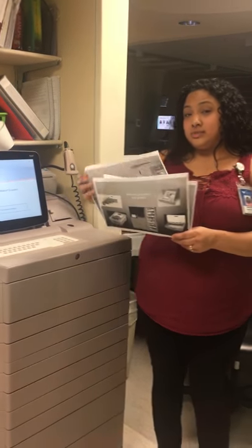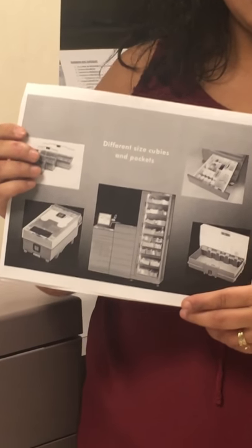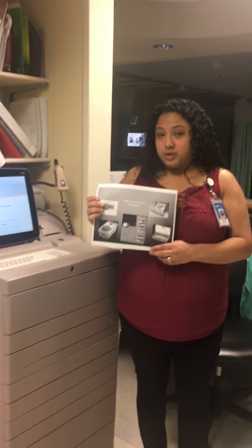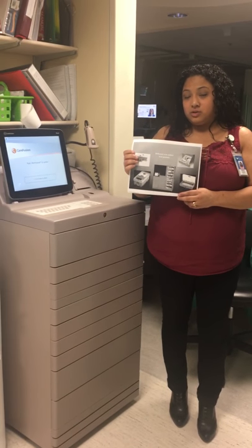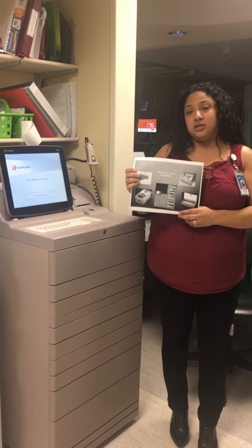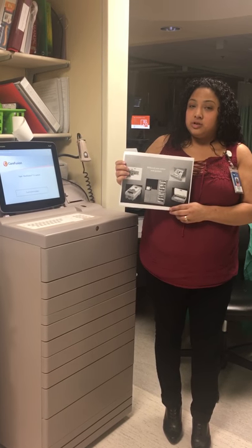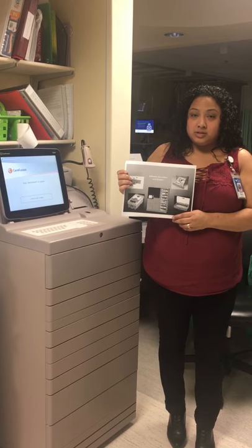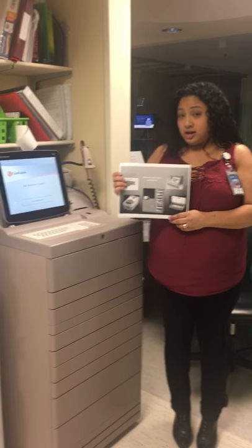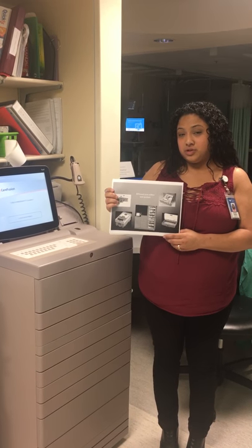Pyxis has different sized Cubies. It has 1x1s, 1x2s, 1x3s, and full height Cubies which are 2x1, 2x2, 2x5s, and 2x3s. We also have matrix drawers and towers. Depending on the medication, that is how you will load your medications. For example, you will load tablets in 1x1s, 1x3s, and 1x2s. If you have ciprofloxacin bags, you might want to load those in tower pockets or matrix drawers.